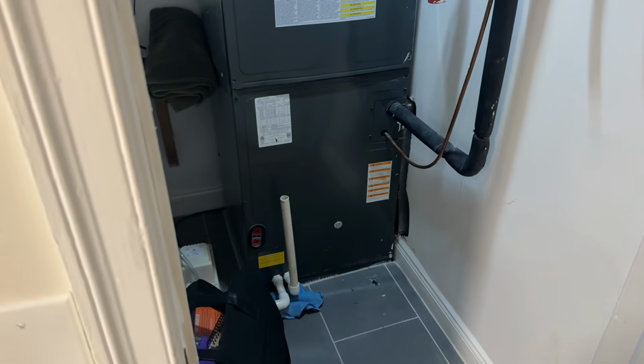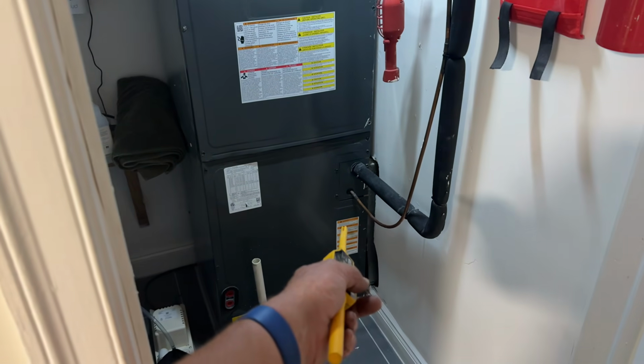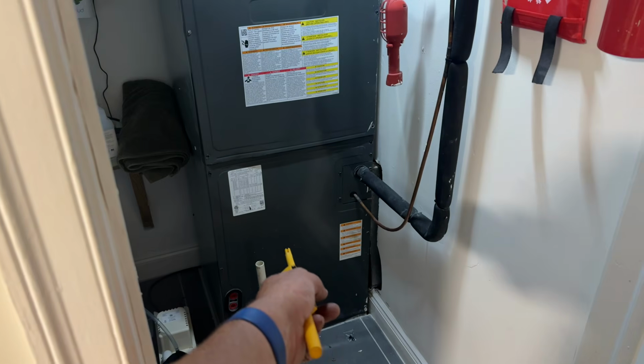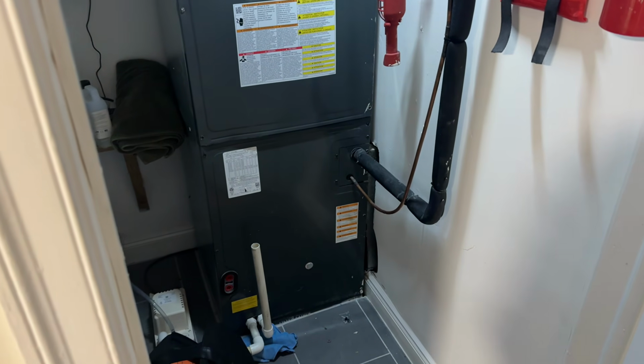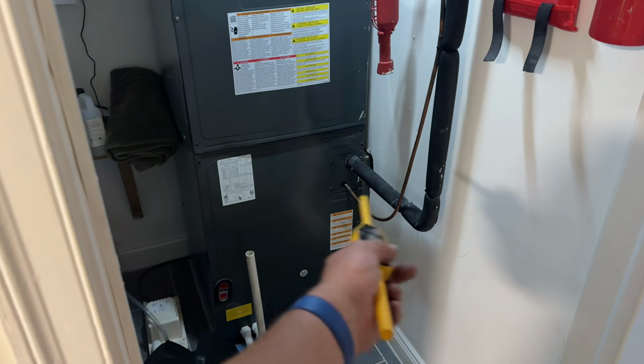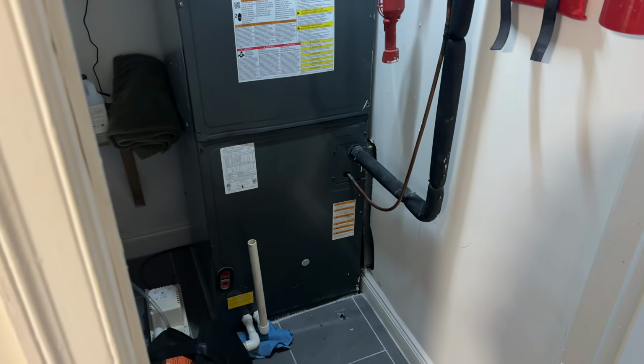And at that moment, ladies and gentlemen, I had that aha moment. Half of the evaporator coil, maybe even less than the evaporator coil, is actually taking in return air. Remember that opening scene? Let's take a look at that again. I just noticed this. They're pulling the air on the side of a coil. They made it like a side return. Oh my God, hacks bring me stacks. They need a new air handler. Or just redo the ductwork and raise up the air handler and bring the return air more underneath, or just maybe do an open air return. Disgusting.